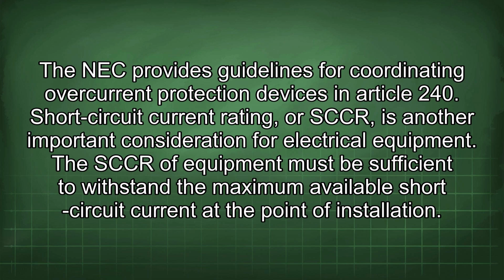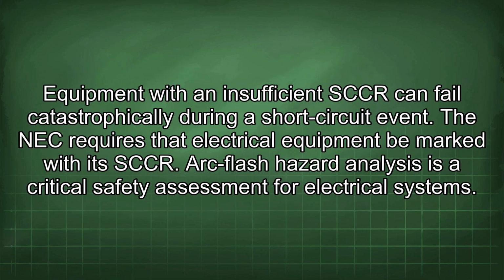Short circuit current rating, or SCCR, is another important consideration for electrical equipment. The SCCR of equipment must be sufficient to withstand the maximum available short circuit current at the point of installation. Equipment with an insufficient SCCR can fail catastrophically during a short circuit event. The NEC requires that electrical equipment be marked with its SCCR.